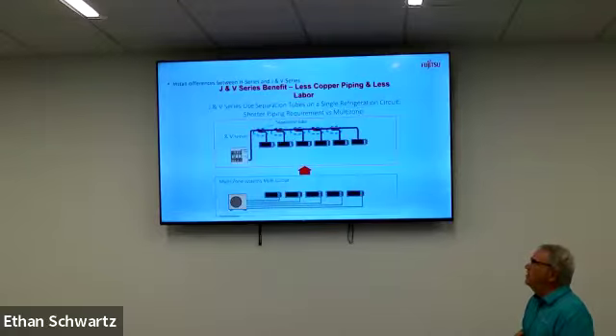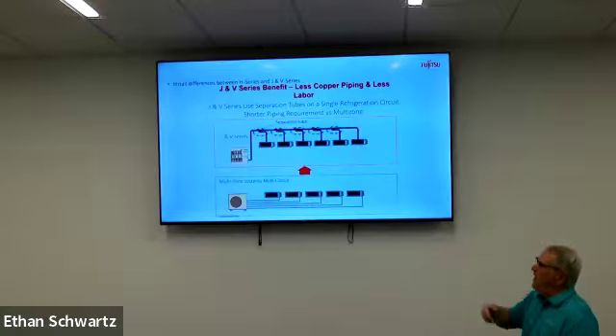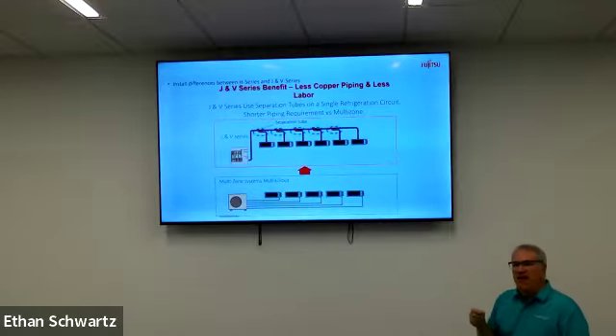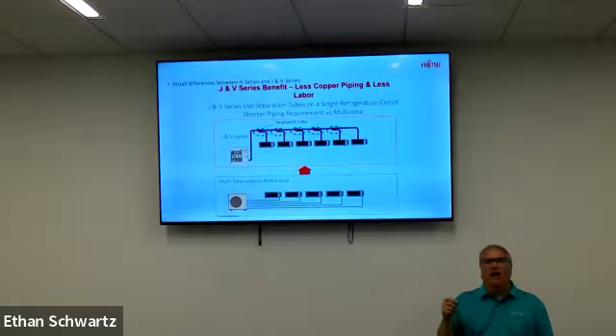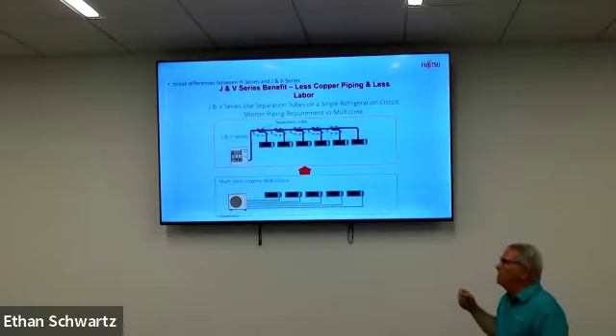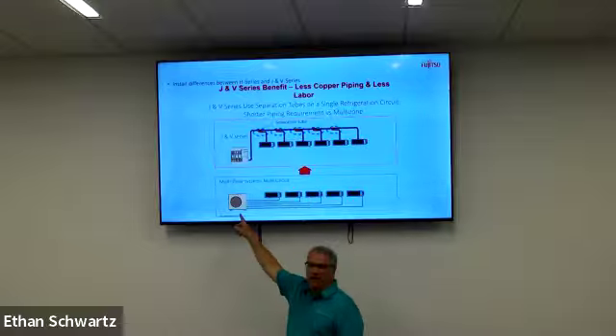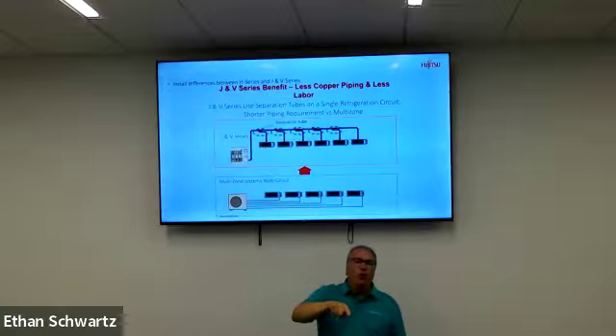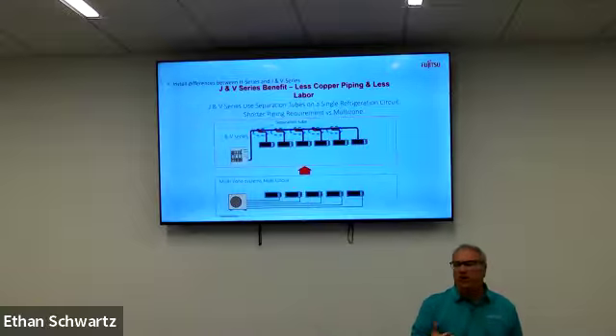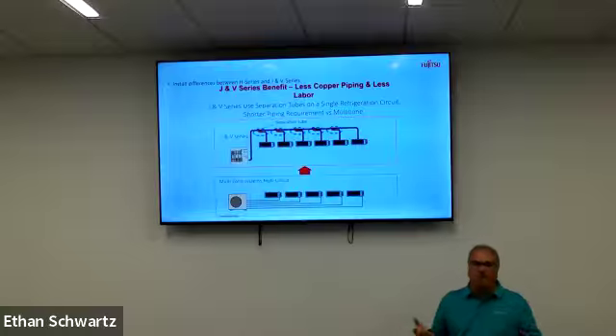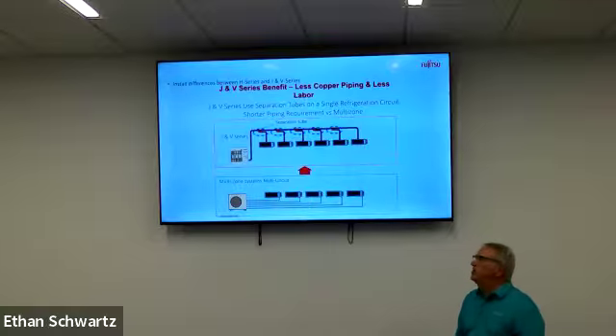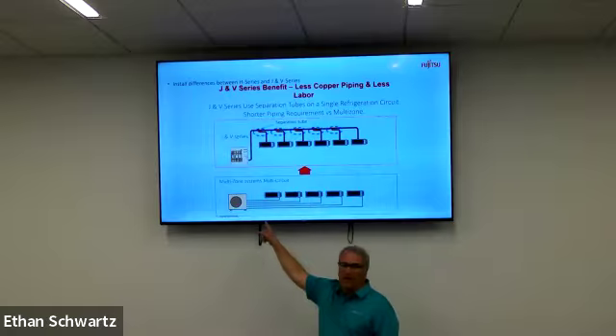No home run line sets with VRF, and we have one for each indoor unit on the mini splits. That's true for any manufacturer. And along with that, from a service aspect, but also an application aspect, the electronic expansion valves for mini splits are located in the outdoor unit.